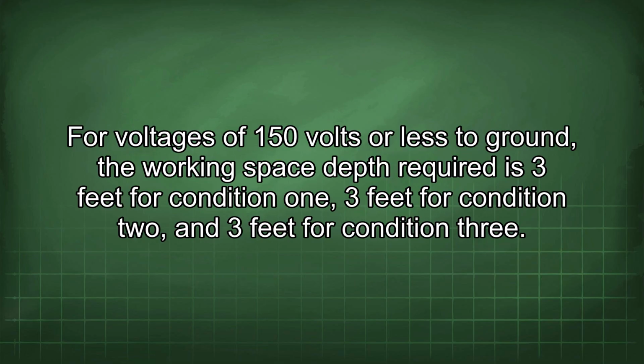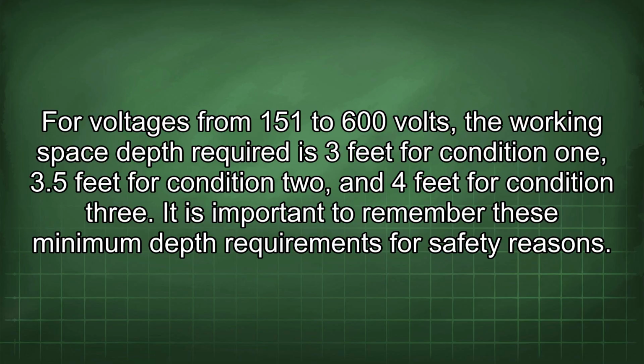For voltages of 150 volts or less to ground, the working space depth required is 3 feet for Condition 1, 3 feet for Condition 2, and 3 feet for Condition 3. For voltages from 151 to 600 volts, the working space depth required is 3 feet for Condition 1, 3.5 feet for Condition 2, and 4 feet for Condition 3. It is important to remember these minimum depth requirements for safety reasons.